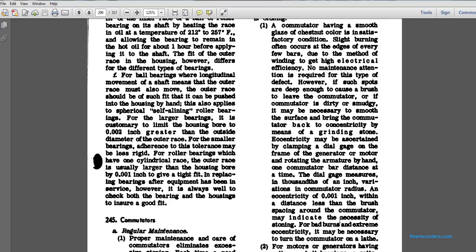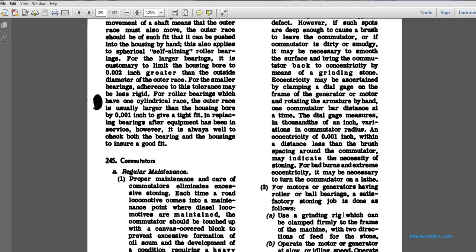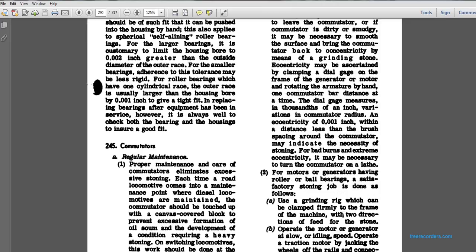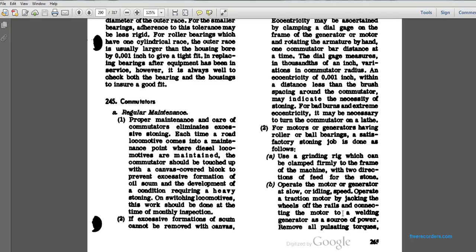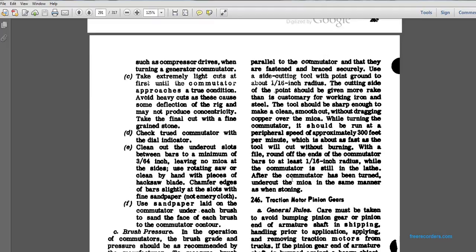For bad burns or extreme eccentricity, it may be necessary to turn the commutator on a lathe. For the motors or generators having roller or ball bearings, a satisfactory stoning job is done as follows. Use a grinding rig clamped firmly to the frame of the machine with two directions of feed for the stone. Operate the motor or generator at slow idling speed. Operating the traction motor, jack the wheels off the rails, connecting the motor to a welding generator as a source of power, and remove all pulsating torques, such as compressor drives, which would turn a generator commutator.